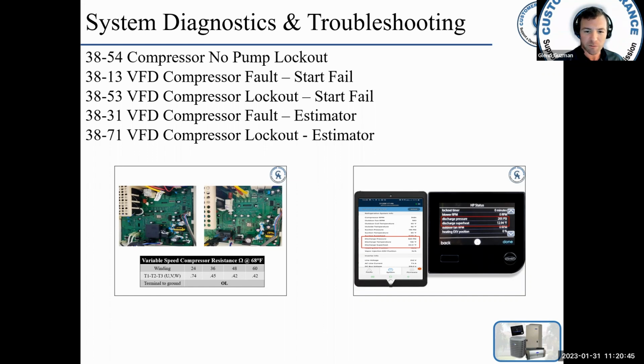3831 is a compressor estimator fault and the lockout. These are rare. I don't know if I've seen one of these codes occur, but it's used in the compressor starting process. When the fault is active, the PEV will open and the compressor will continue to attempt to restart. After 3 codes of 3831, you get the 3871 and a 4-hour lockout. You could have high starting torque, possible compressor damage. Ensure the VFD is correct for the compressor that you have, and ensure that all the parts are correct for the model being serviced. You may have compressor damage if you have that. But again, in the last couple of years, I don't think I've seen the 3831 or 3871, at least that I'm aware of.